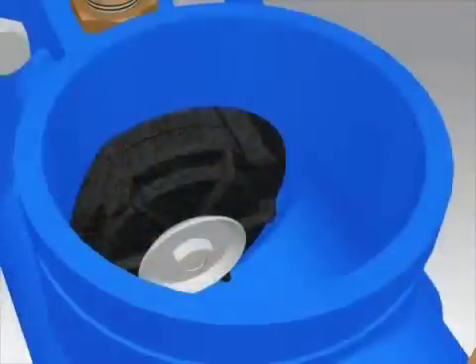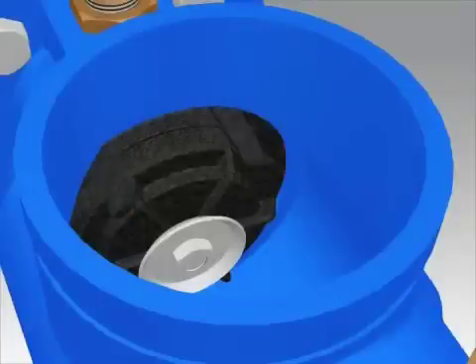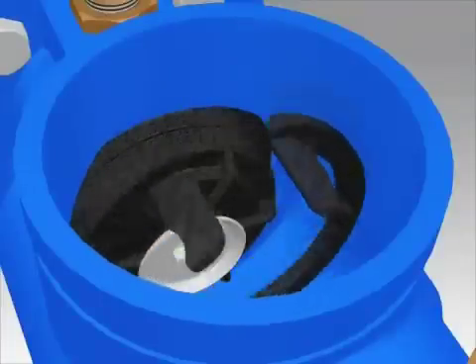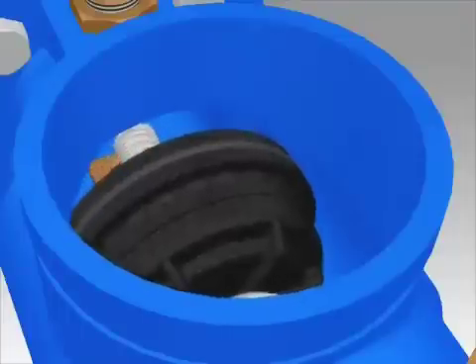To remove the number 1 check valve, locate the two tabs of the plastic retainer at the top of the number 1 check. Grasp the two tabs and squeeze ends together. Then pull straight back and the retainer should slide out of the groove. Remove the number 1 check assembly.